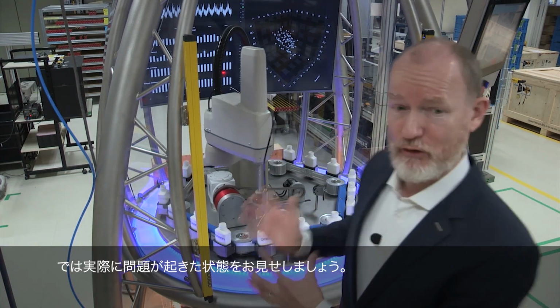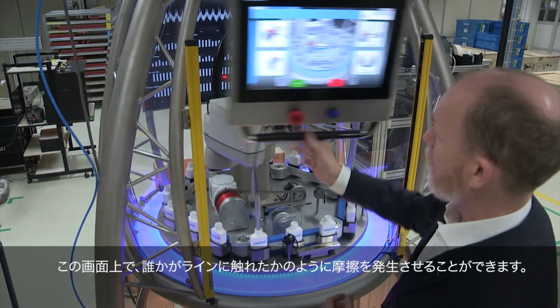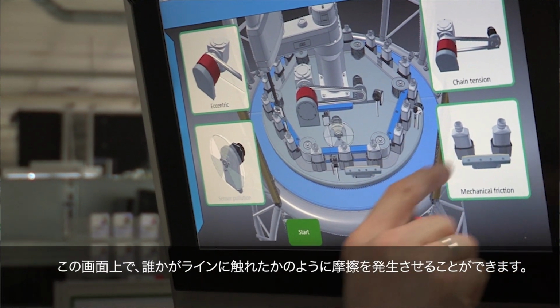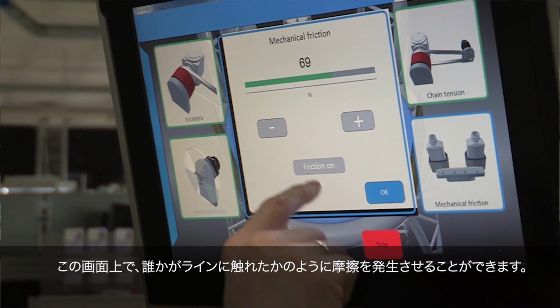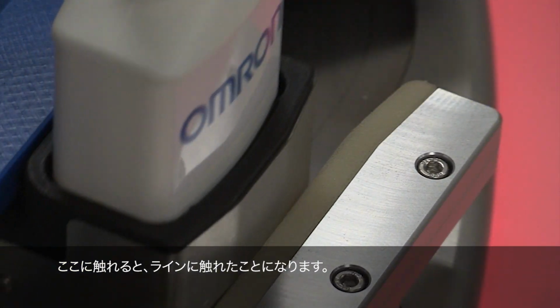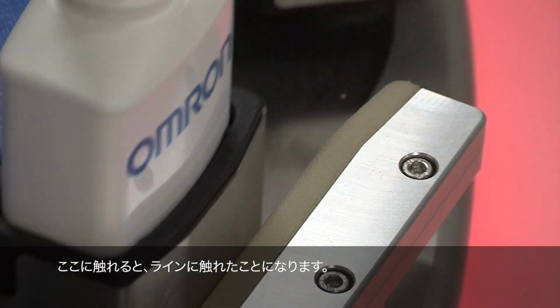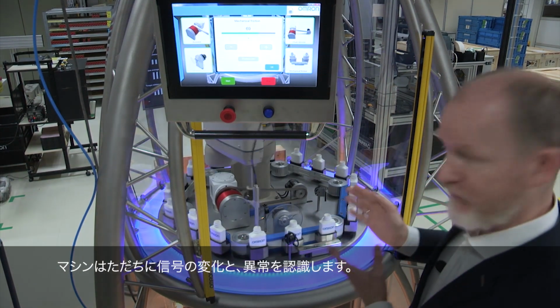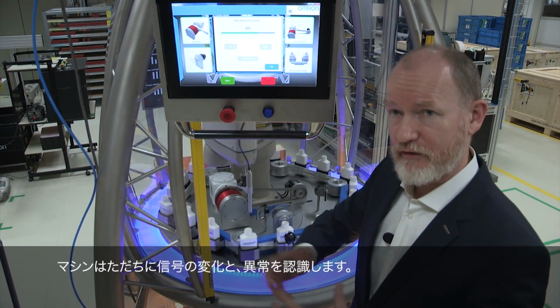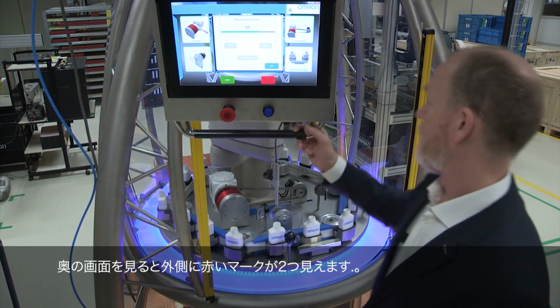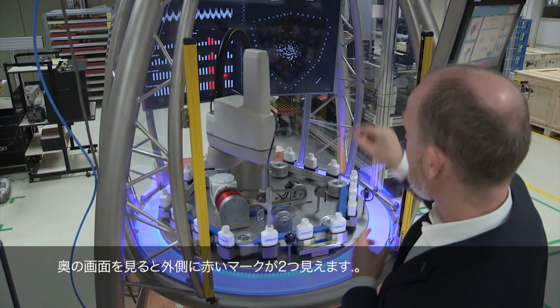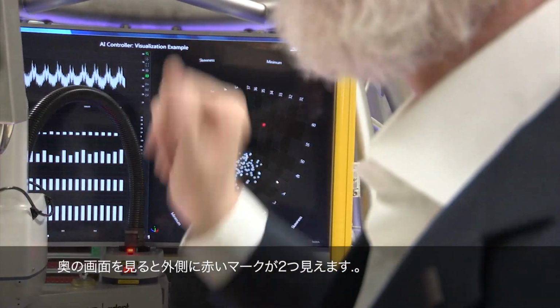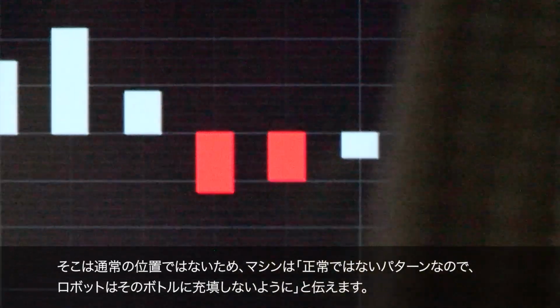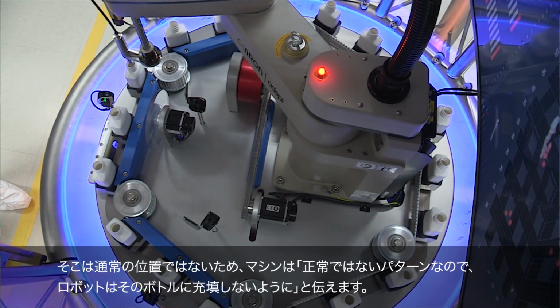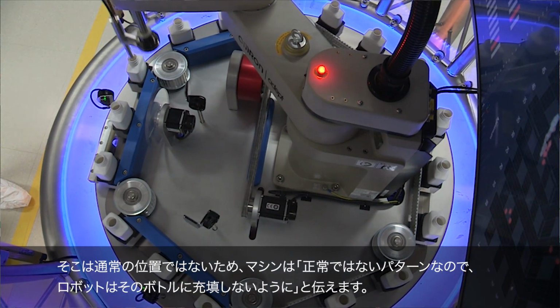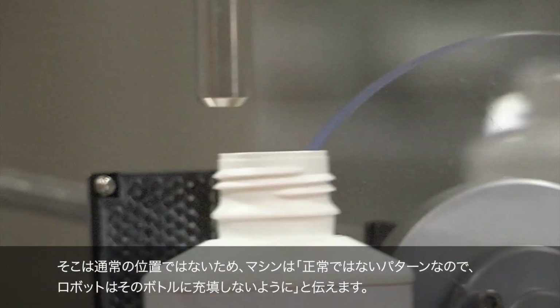And I can introduce some problem here. Because if I look on this screen, I can create some mechanical friction, as if somebody is touching your line. So if I hit it, then you will see, oh, the line is touched. It's immediately recognized that the signals have changed, and this is not normal. And if you look on the screen over there, you see the two red marks. They are in the outer space, the not normal space. So the machine has recognized, hey, I've now seen patterns that are not normal, and I should ask this robot not to enter the bottles.